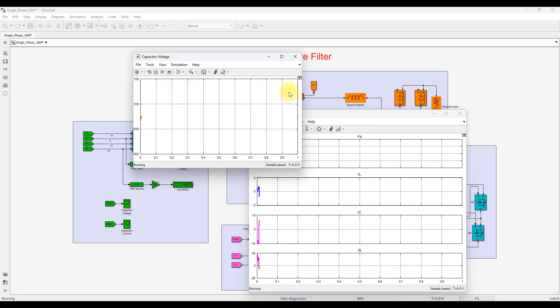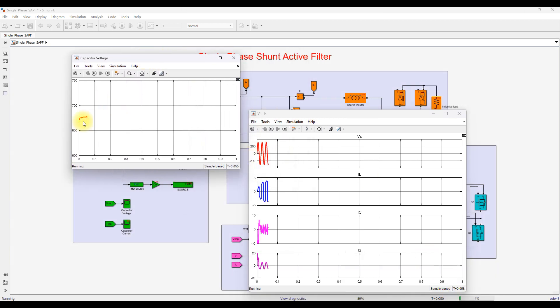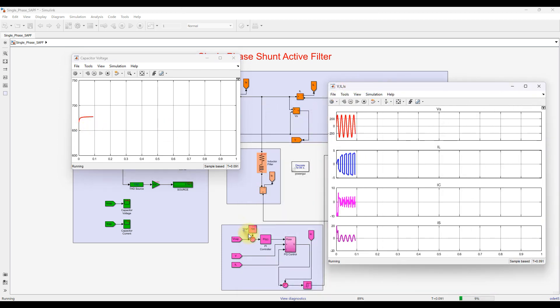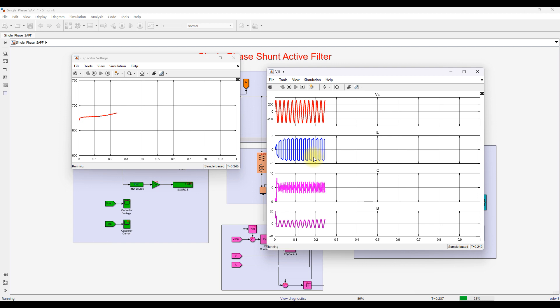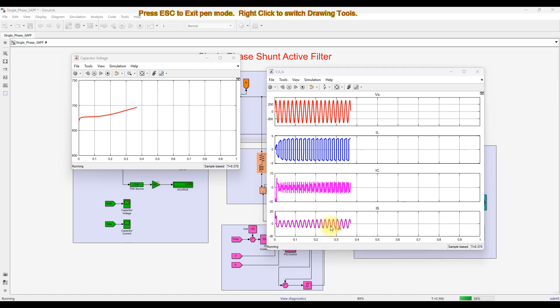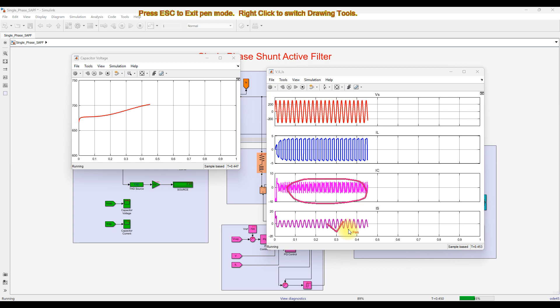Here you can see the capacitor voltage is initially maintained at around 670 volts, while the reference voltage is set to 700 volts, so the capacitor voltage is charging towards 700 volts. You can also see that the source current is sinusoidal while the load current is non-sinusoidal because of the nonlinear load. The nonlinear load produces a non-sinusoidal current, but the source current is sinusoidal.